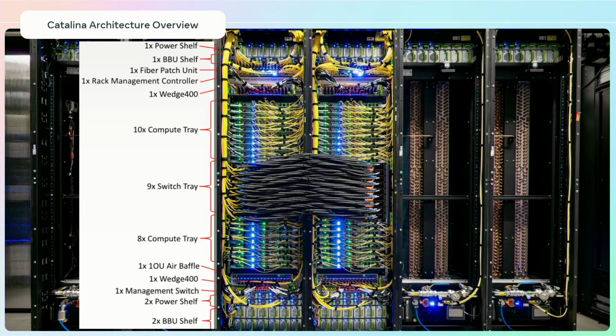Looking at a bit more detail at the rack itself, these are the different components we have. We have power supplies within the racks along with BBUs, or battery backup units. These take in the 480 volts or 277 volts single phase, and convert it to 48 volts DC, distributed through the bus bar in the back, powering all of the individual server blades, NV switches, and networking devices within the rack. At the top and bottom of the rack, we have one power shelf, one BBU, and then two more at the bottom of each.